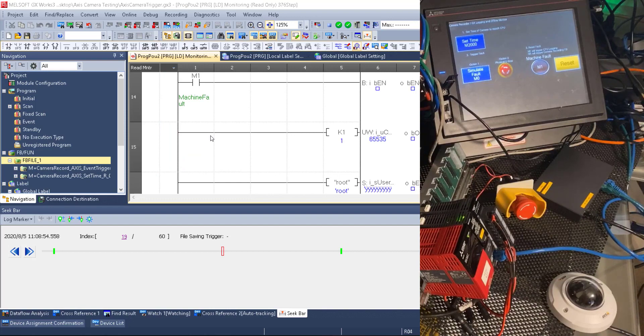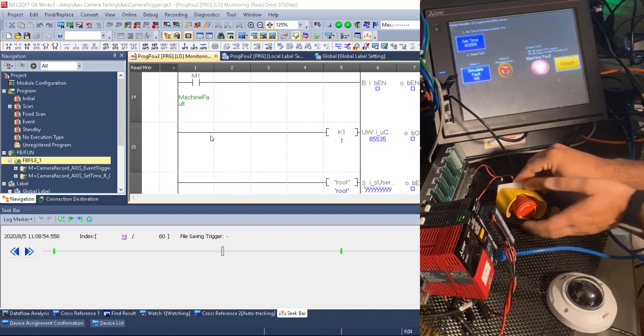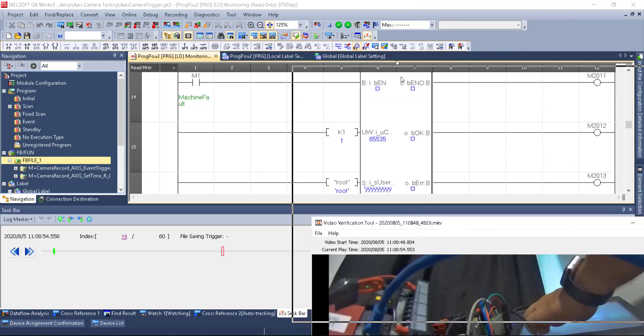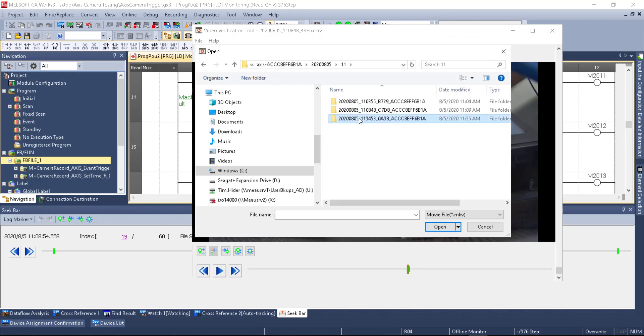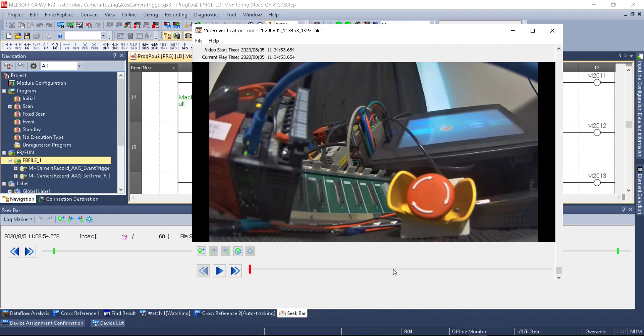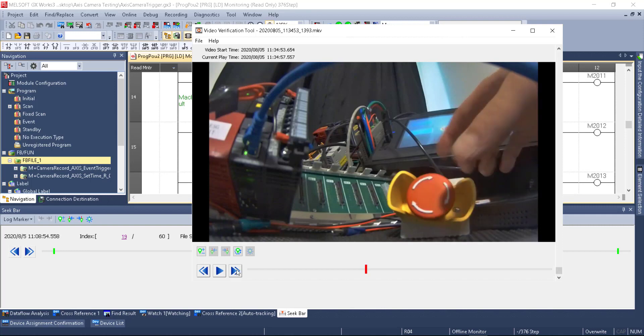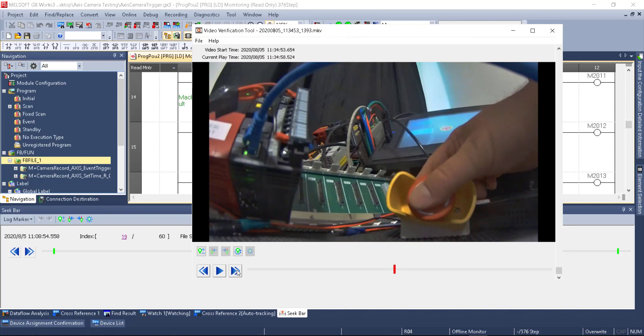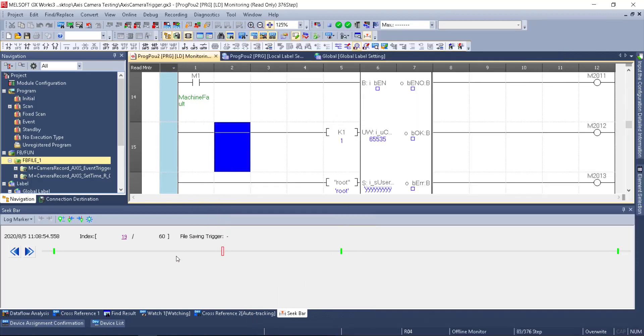Now I'll quickly do a live demo. I hit the physical e-stop, we get our fault, release the e-stop, and clear the fault — that should have recorded. Let's verify: first we check the video file by switching to the video folder. At 11 o'clock we have a third folder — that's a good sign. Opening it and going to about the middle, there I am pressing the e-stop. I can click through each frame individually and see the exact moment I pressed it, or if there was an equipment problem — something jammed, a switch or dog not made, incorrect product on the line — you can see that exact moment.